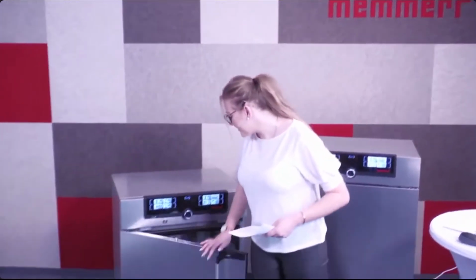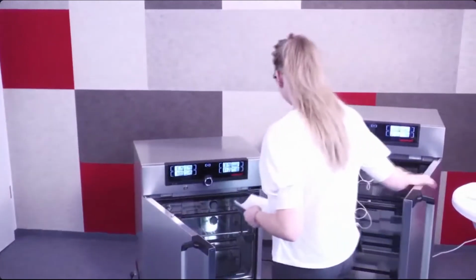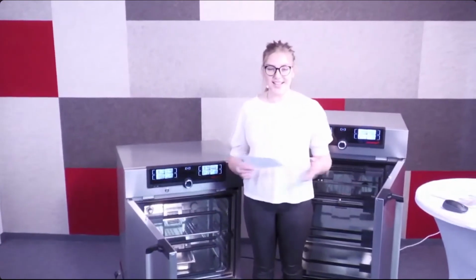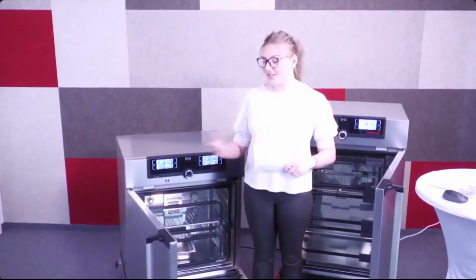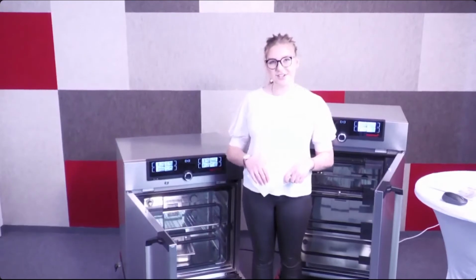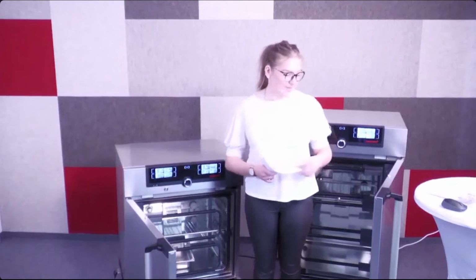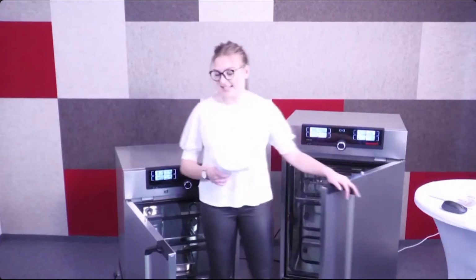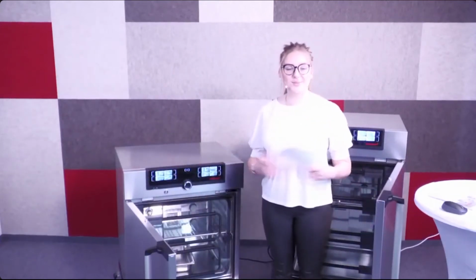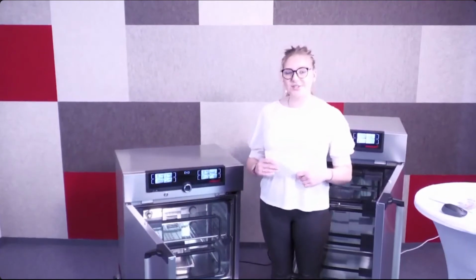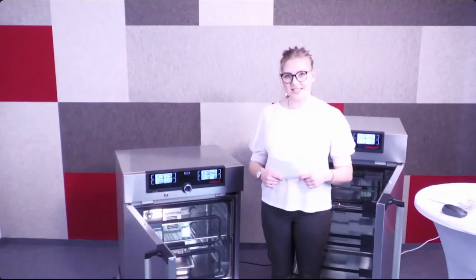When opening up the doors, we can already see they both open up on different sides. Well, this is another one of Memmert's key features. We're very flexible, and we have the ability to really adjust to the customer's needs. The door hinges, for example, might be a very underestimated feature, but they're frequently used, especially in small labs, where space oftentimes is a luxury and where we're running out of space quite quickly. This is the Memmert standard configuration with the hinge on the right-hand side, opening up on the left-hand side. This can either be conveniently ordered when placing your initial order with us, or it can be changed in retrospect by a technician in several minutes only.